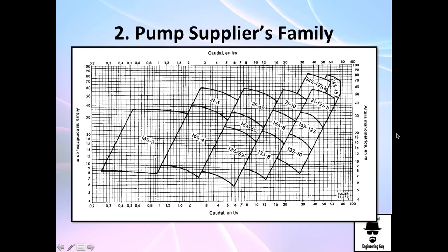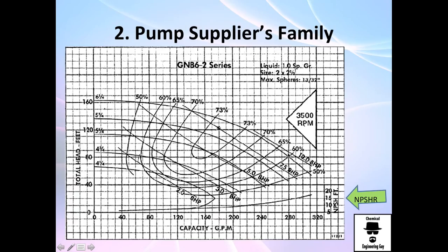Once you find out, you ask your supplier, and they'll give you the pump diagram or curve. Here you can see head versus Q, and you can see how the efficiency—the maximum efficiency is 73 percent—the sizes of diameters, the NPSH, the velocity that must be operated, and essentially that's it.